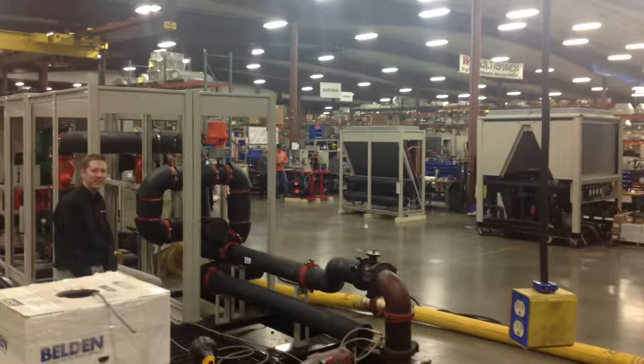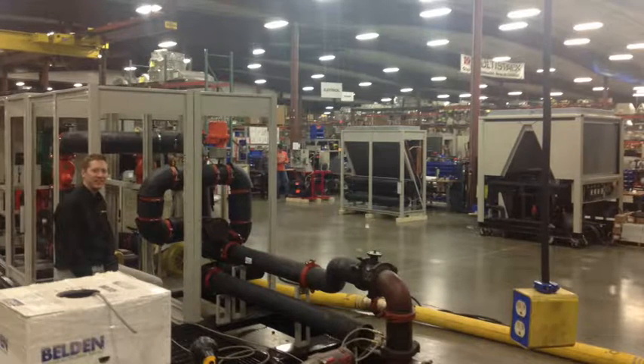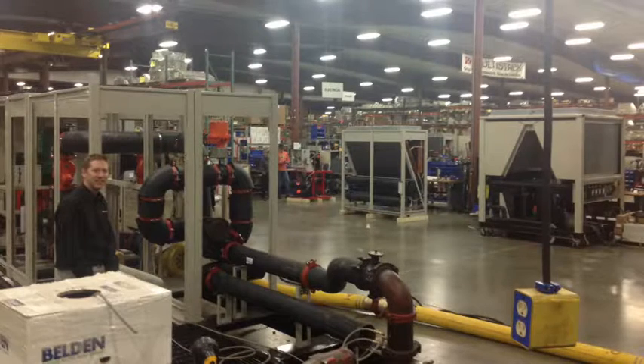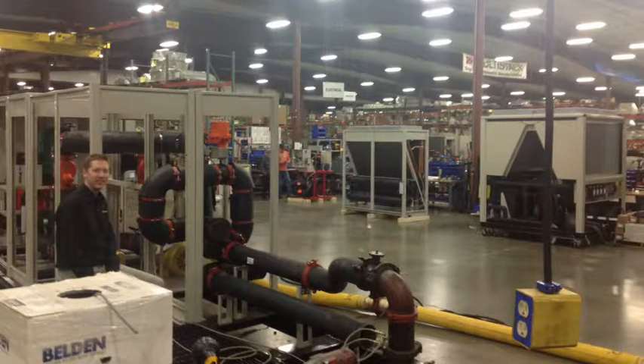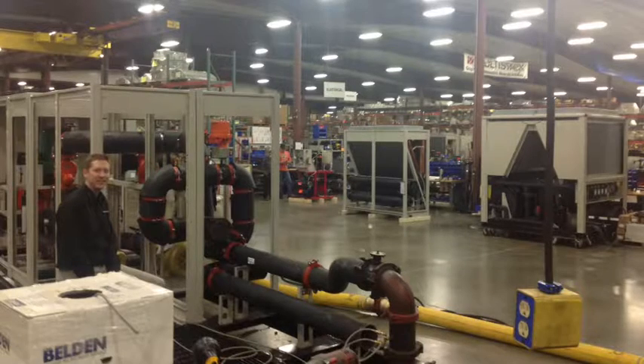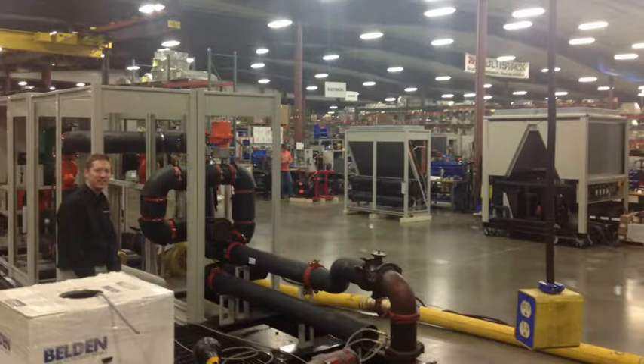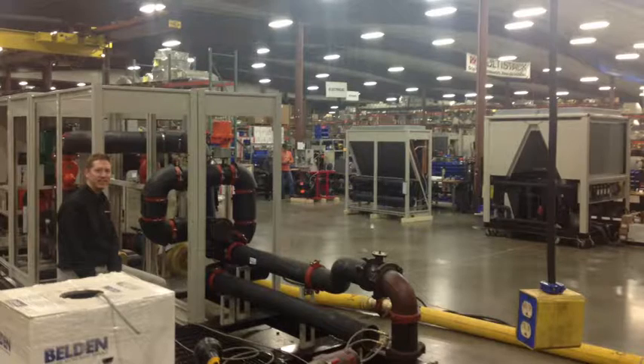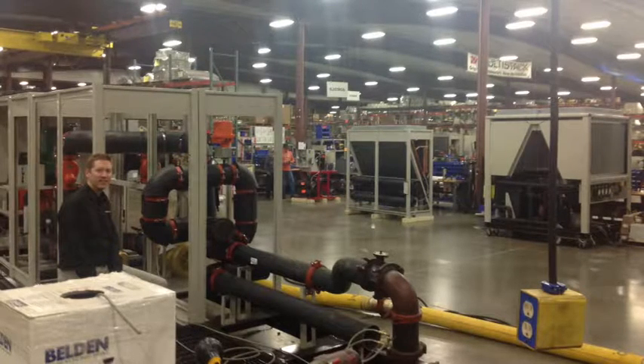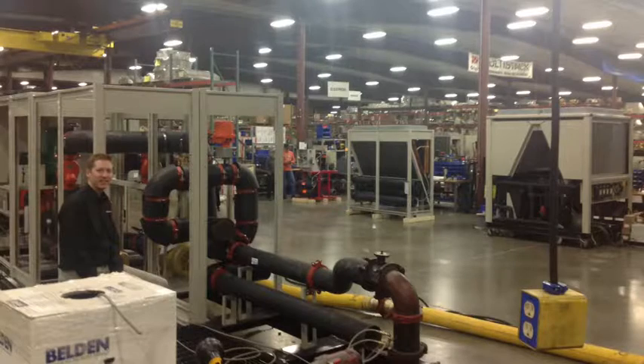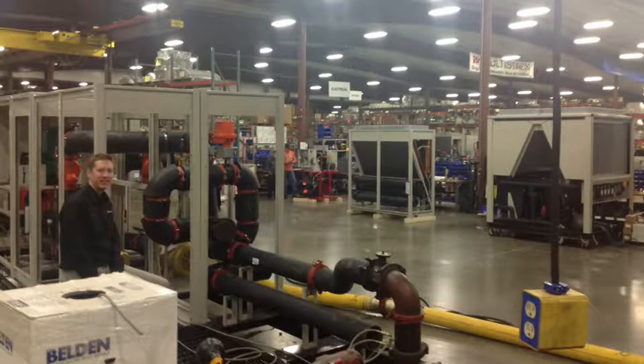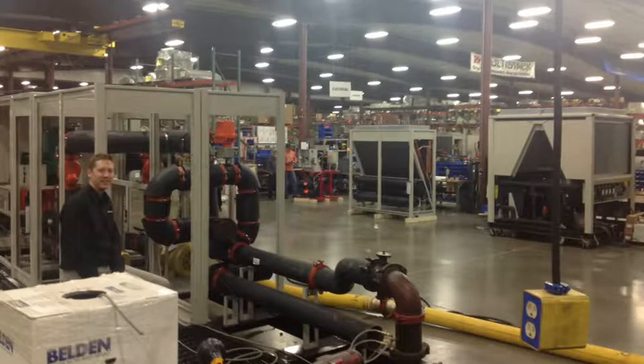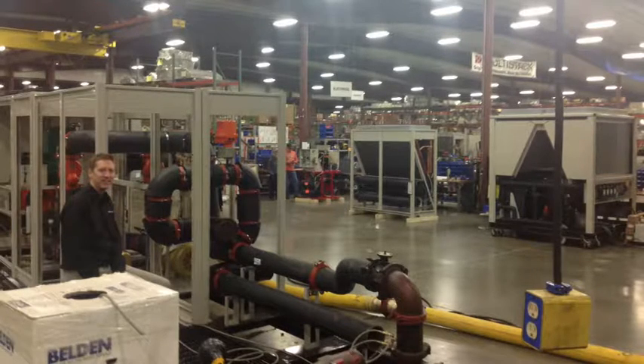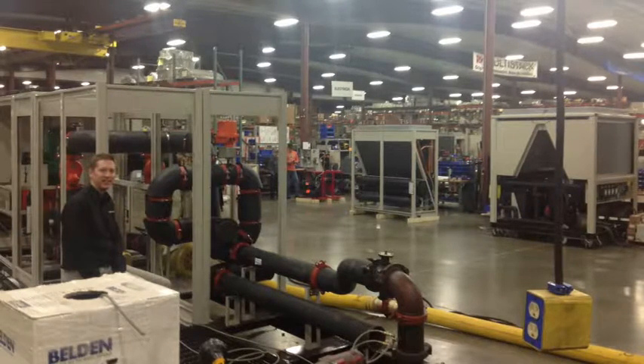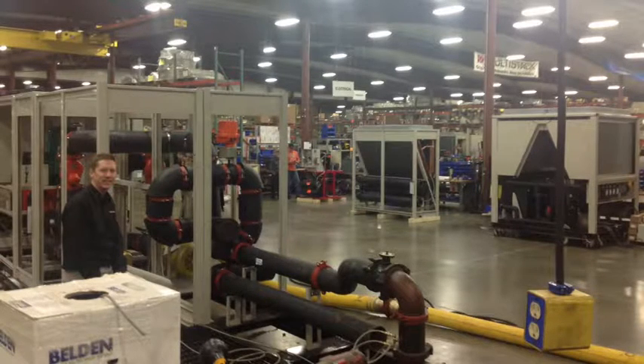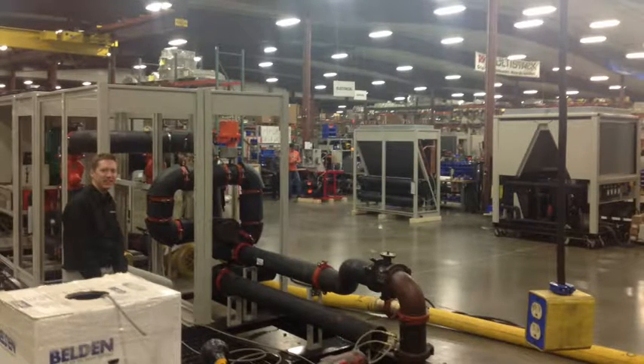The other important part of this tour is the piping and Belimo actuator to Mike's left. That system of piping and valves is the free cool bypass. Because we only have 2 free cooling modules and 7 mechanical modules, we need to bypass a certain amount of water during free cooling operation. The bypass valve and free cooling controller will accomplish this. Until the free cooling modules are installed, this will be deactivated and all of the water will pass into the mechanical modules. Now we'll turn the microphone over to Mike Orlikowski, Key Accounts Manager at Multistack, for a tour of the free cooling module piping.